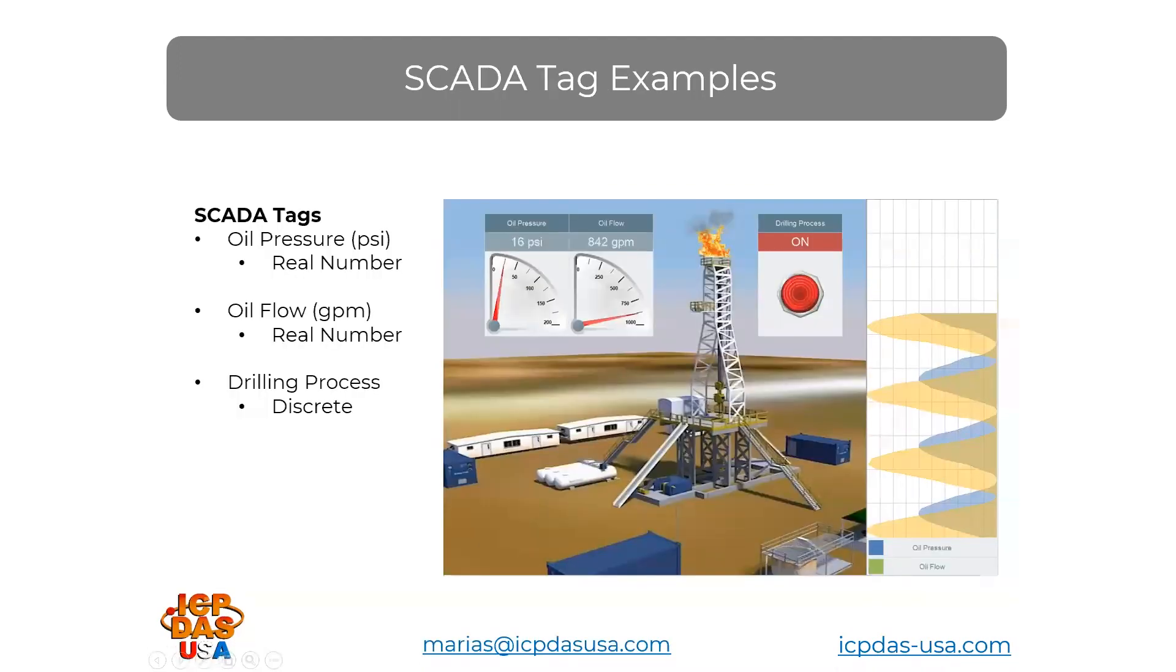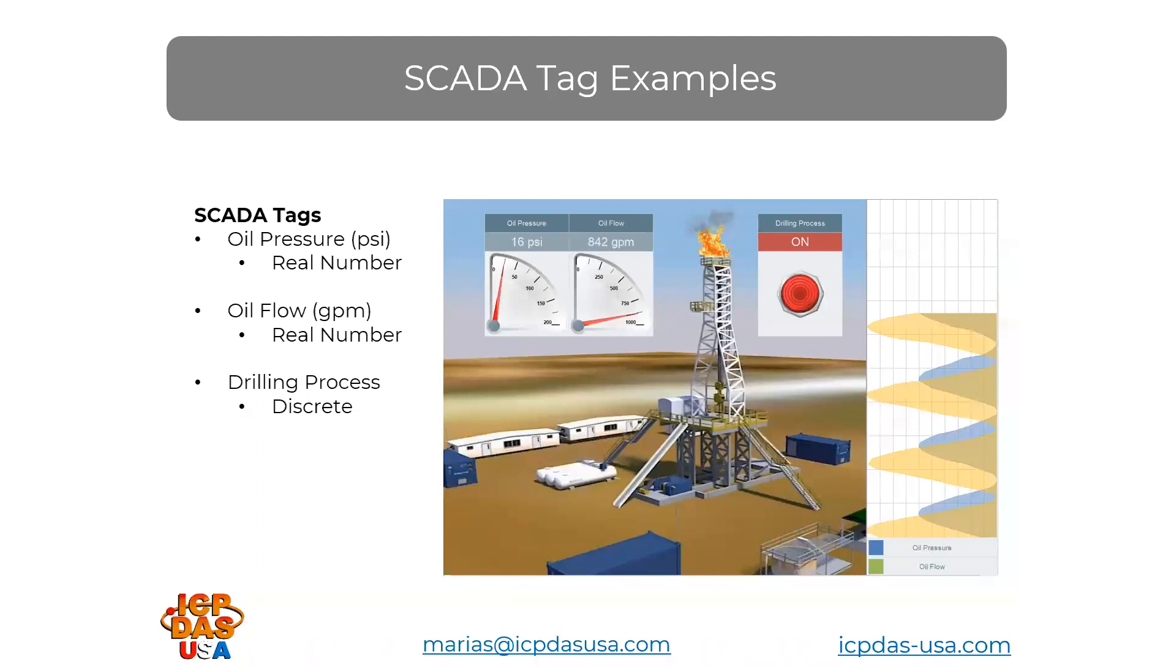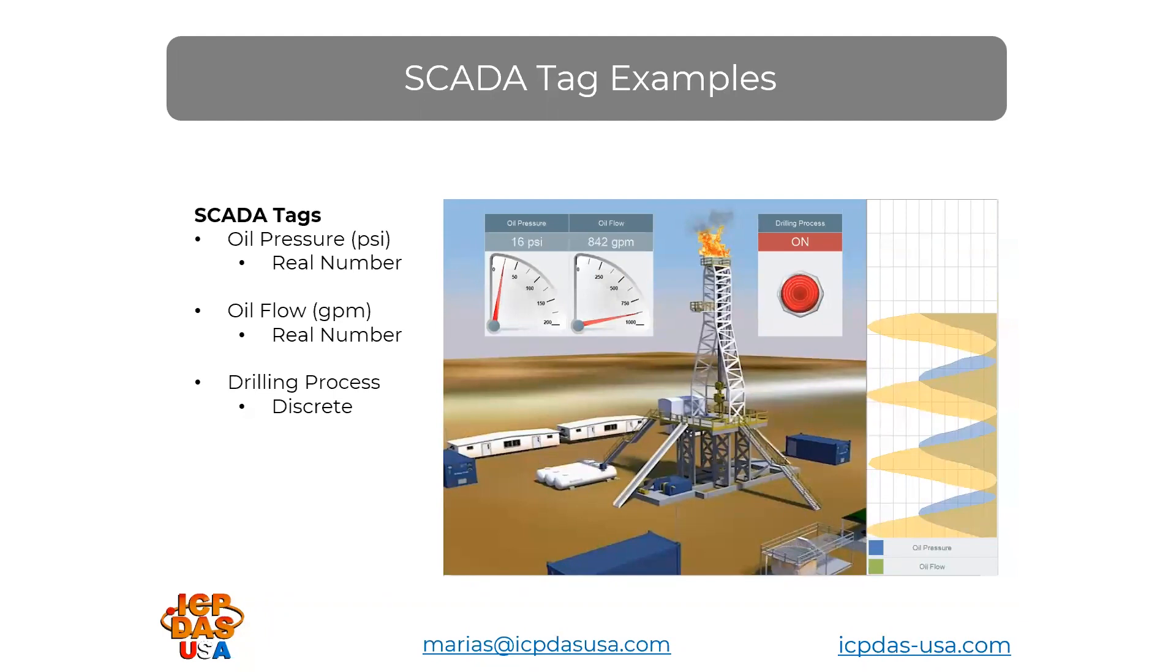In this oil drilling application, our ET-7017 Modbus TCP-based data acquisition modules are networked over Ethernet cabling to a PC with an Ethernet switch. ET-7017 has 4 to 20 milliamp inputs that are mapped to gather pressure and oil flow in an oil drilling application. There's an on button that when it's pushed, the drilling process is either on or off. It shows in red when it's on and dims when it's off. This application is accessible over the AVEVA mobile app, a web browser, or locally on-site through the SCADA application running on Windows 11 computer. The oil pressure is defined in the application as a real number. The flow of oil in gallons per minute is also defined as a real number. The drilling process is a Boolean discrete variable that's either on or off.